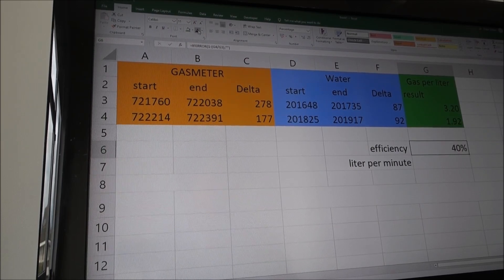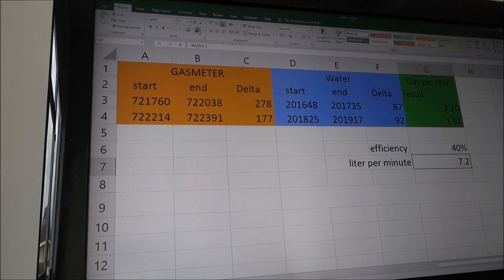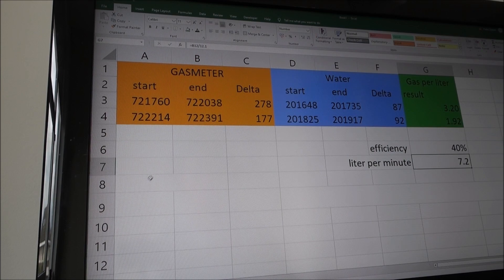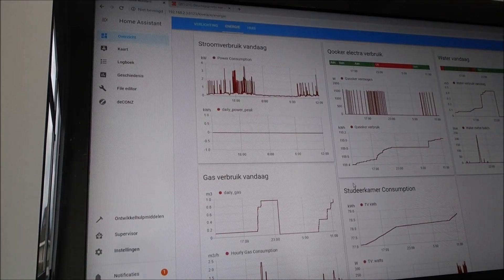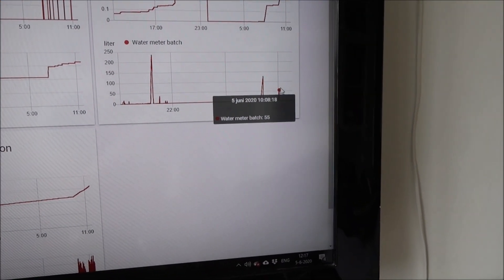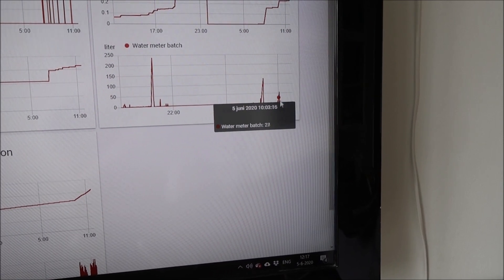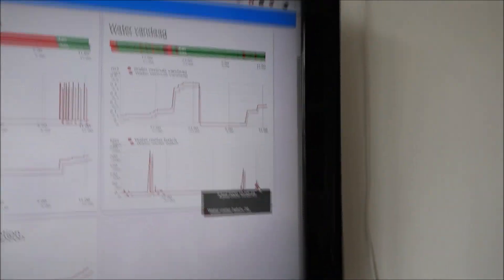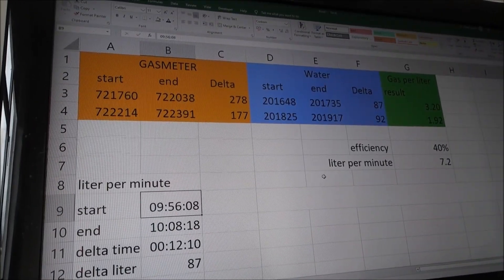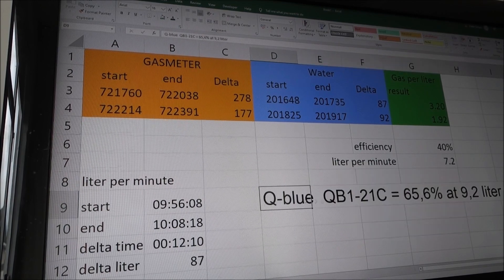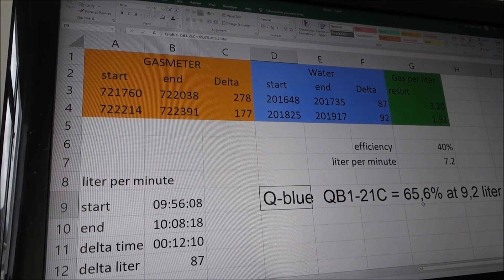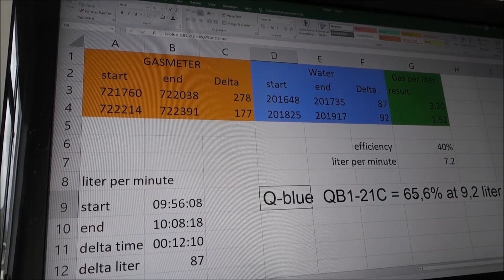The efficiency is 40 percent, at a flow rate of 7.2 liters per minute. The flow rate was determined using my water sensor, where each spike corresponds to a shower or bath event. The Q Blue shower heat exchanger 21C is specified at an efficiency of 65.6 percent at a flow of 9.2 liters per minute.